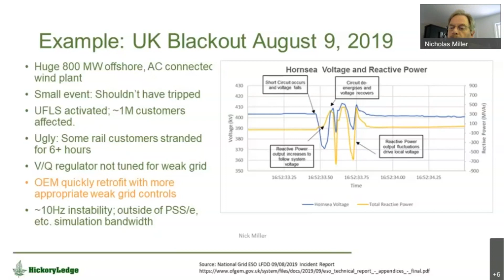What happened was, during the course of commissioning this plant, they had off-the-shelf controls in the wind plant. They hadn't set up the controls for weak grid. And they saw this happen. They went out, and basically within 24 hours, they had the problem, the risk, removed by having the right controls in place. So scary, cautionary, but also in this particular case, it's something they could have seen coming had they been watching, and the OEMs were quite capable of making the plant behave itself properly.